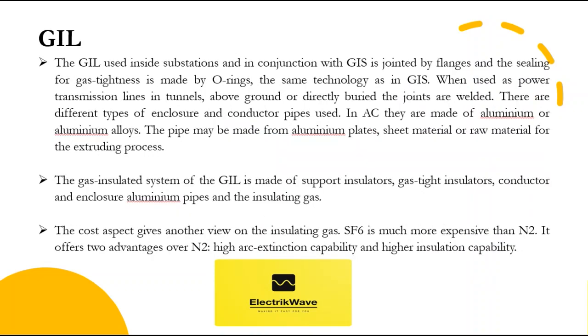The GIL used inside substations and in conjunction with GIS is jointed by flanges, and the sealing for gas tightness is made by O-rings — the same technology as in GIS. When used as power transmission lines in tunnels, above ground, or directly buried, the joints are welded. There are different types of enclosure and conductor pipes used. In AC applications they are made of aluminum or aluminum alloys. The pipe may be made from aluminum plates, sheet material, or raw material for the extrusion process.